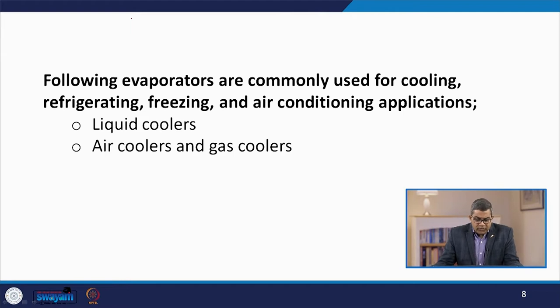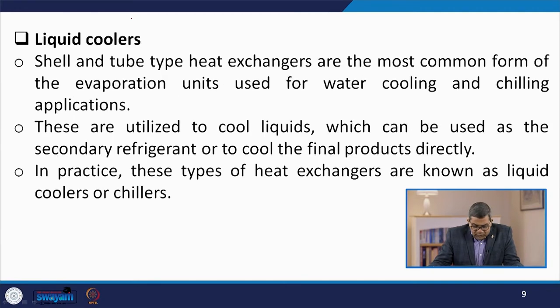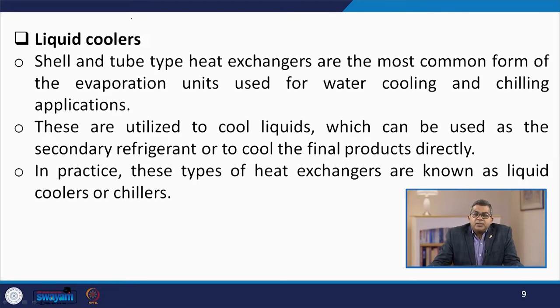Various evaporators are commonly used for cooling, refrigerating, freezing, and air conditioning applications like liquid coolers, air coolers, and gas coolers. Shell and tube type heat exchangers are the most common form of evaporation units used for water cooling and chilling applications. These are utilized to cool liquids which can be used as the secondary refrigerant or to cool the final product directly. In practice, these types of heat exchangers are known as liquid coolers or chillers.